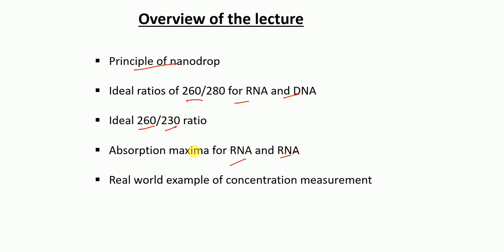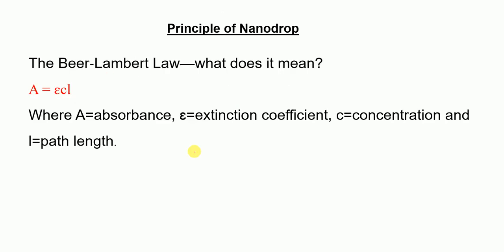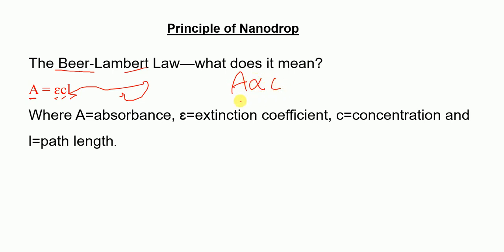First, let's talk about what is the principle of nanodrop instrumentation. The principle is based on the Beer-Lambert law, which states that absorbance equals epsilon times concentration times path length. This means that absorbance is directly proportional to the concentration — the higher the absorbance, the higher will be the concentration.